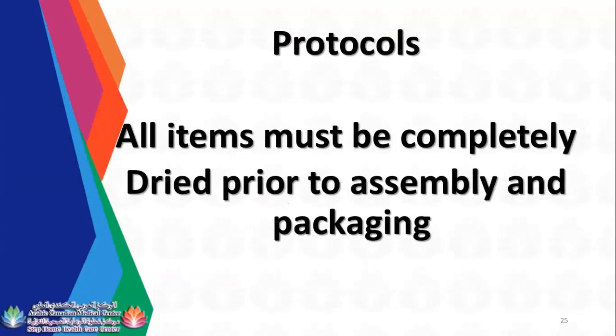So, protocols: all items must be completely dried prior to assembly and packaging. Before you do pouching, before you place instruments in the rigid container, you need to follow the protocols. You need to dry the instruments prior to placing them. Wet instruments are not allowed to be packed or pouched because they can generate more moisture.